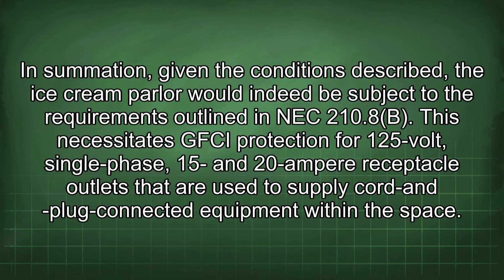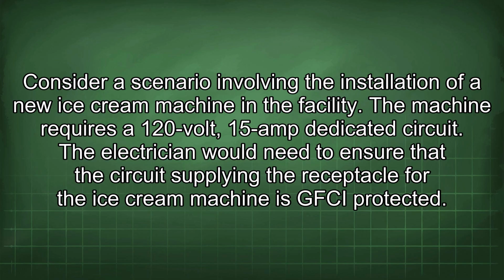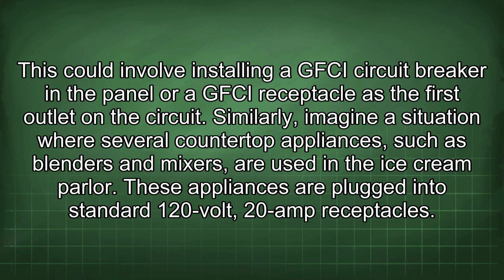In summation, given the conditions described, the ice cream parlor would indeed be subject to the requirements outlined in NEC 210.8b. This necessitates GFCI protection for 125-volt, single-phase, 15 and 20 ampere receptacle outlets that are used to supply cord and plug connected equipment within the space. Consider a scenario involving the installation of a new ice cream machine in the facility. The machine requires a 120-volt, 15 amp dedicated circuit. The electrician would need to ensure that the circuit supplying the receptacle for the ice cream machine is GFCI protected.